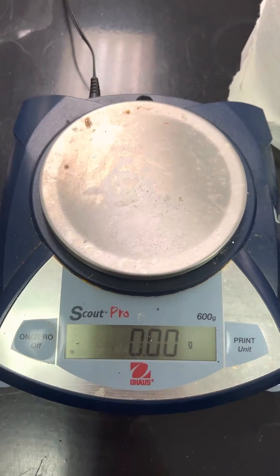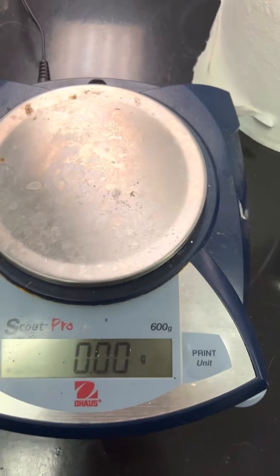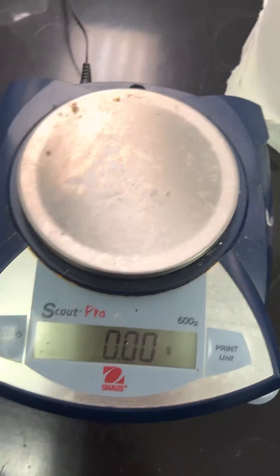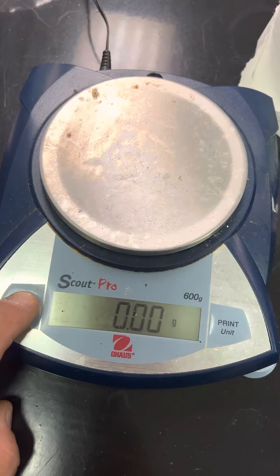This is a calibration adjustment of an Ohaus Scout Pro, or SP602, or any Scout Pro — basically any SP model. You have to shut it off first.